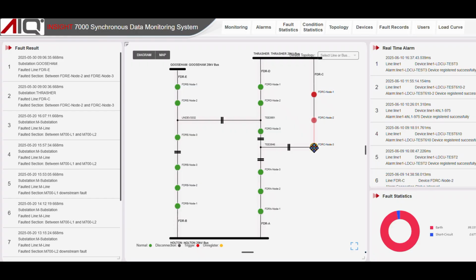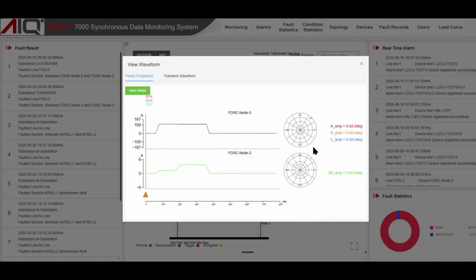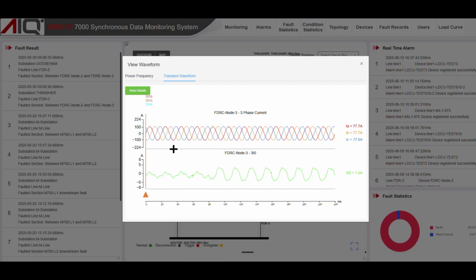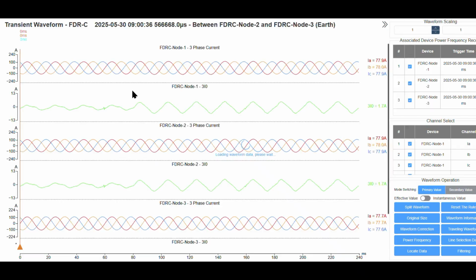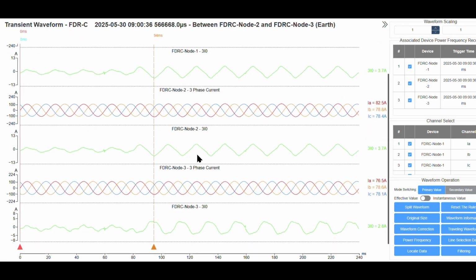Looking then at node 3, the magnitude and phase of the fault current, we can see that the zero sequence current angle is 162 degrees with respect to A phase current and is antiphase as compared to those at nodes 1 and 2. This is also shown in the transient waveform. By clicking on the View Details button, the waveforms from all the nodes can be seen, with the zero sequence currents of nodes 1 and 2 which are in phase, and in node 3 which are antiphase. Because of the time synchronicity between the nodes, the master station is able to time align all the measurements and waveforms from different nodes on the same time axis, thus providing accurate fault localization of the faulted section.